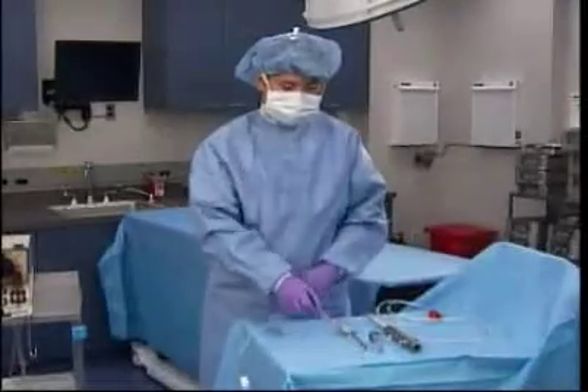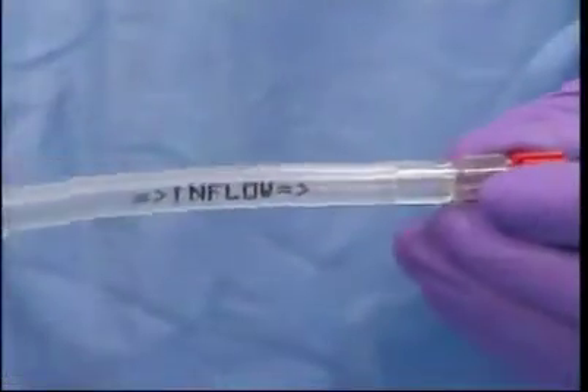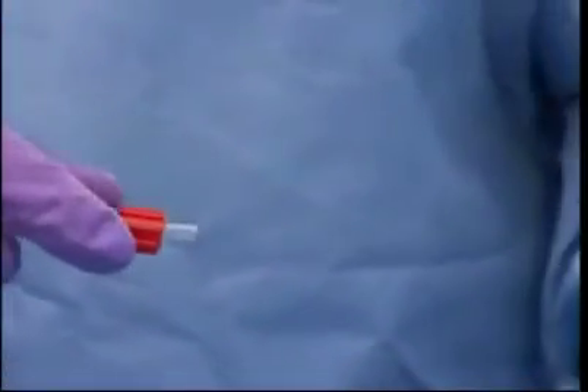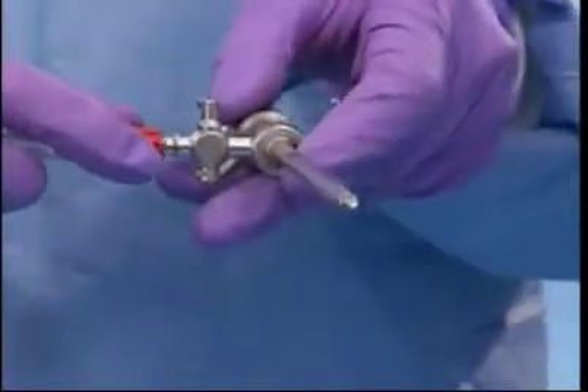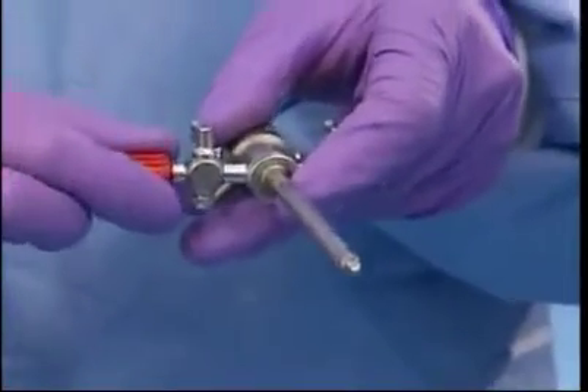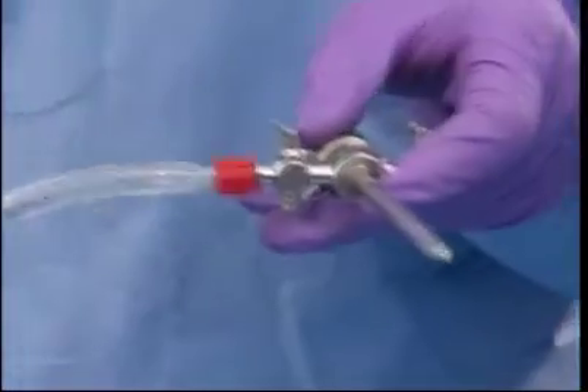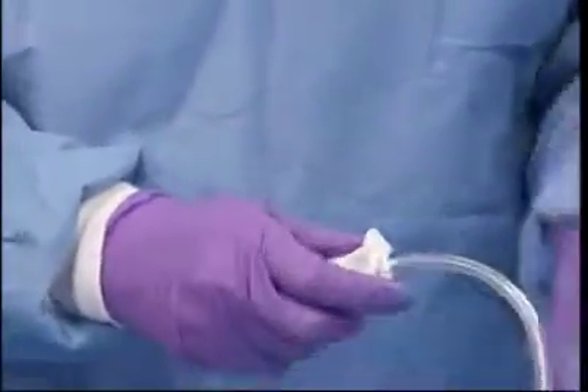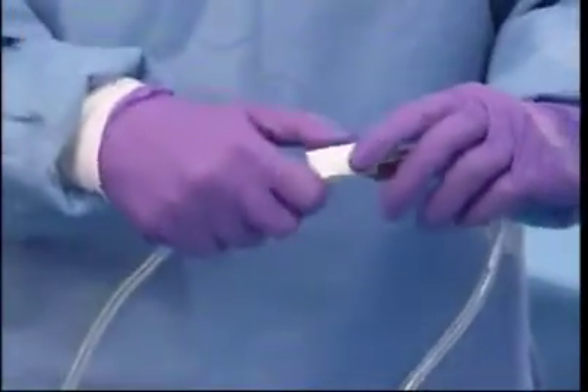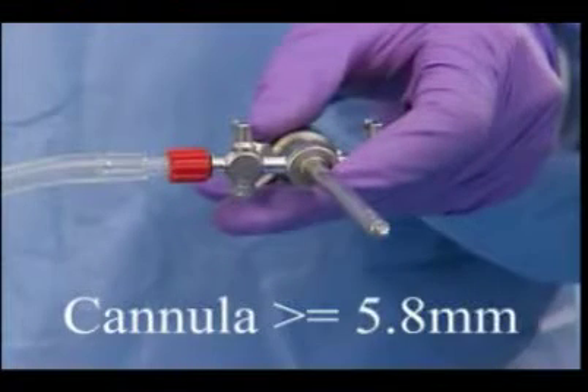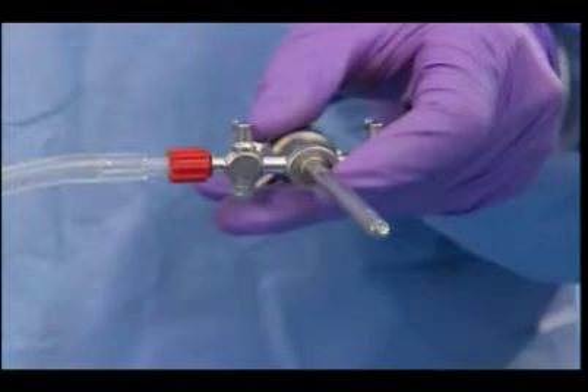Look for the open end of the intermediary tubing labeled inflow. Connect the red luer lock to the scope sheath. Open the white clamp. The FMS Duo system requires a scope sheath with an inside diameter of at least 5.8 millimeters. Ask your DePuy Mitek rep to confirm this is the case before surgery.